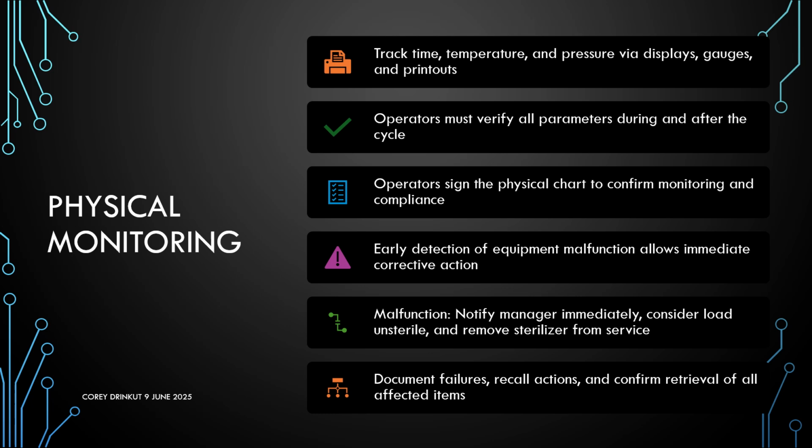Depending on your facility, you will talk to your manager to see what they want to do with that sterilizer at that time. Immediate notification to the department manager is required, and thorough documentation of the failure and recall process is essential to maintain patient safety and regulatory compliance. So if you have anything that's failed, let your supervisor, let your manager know.